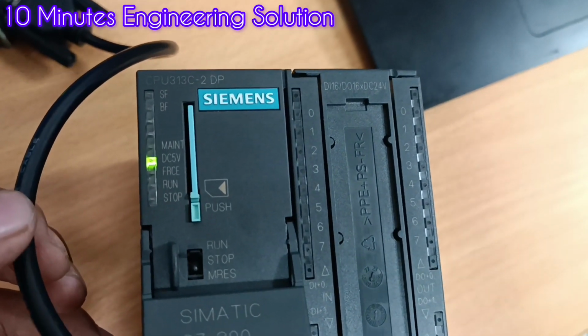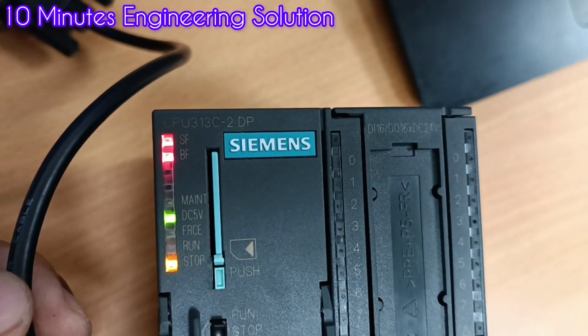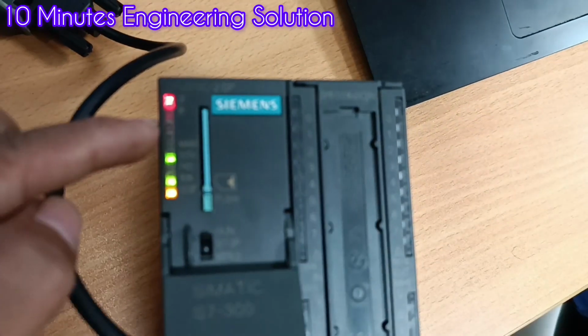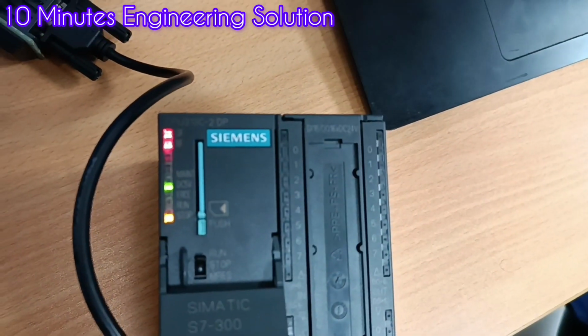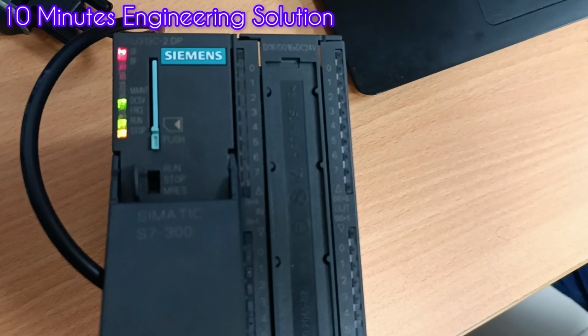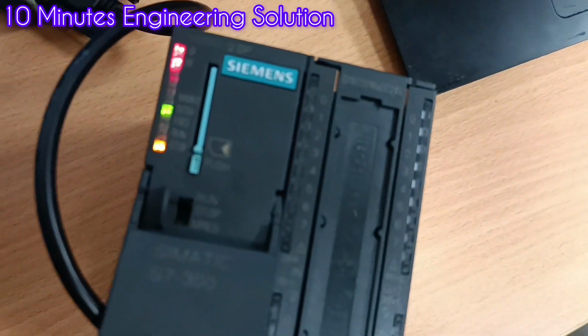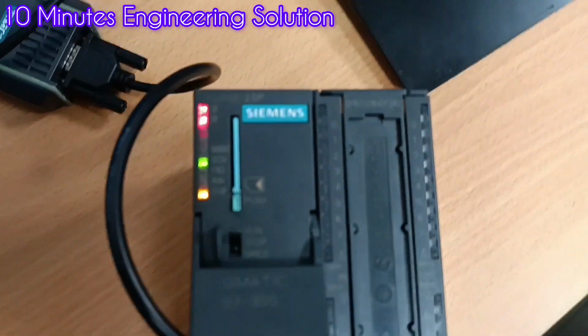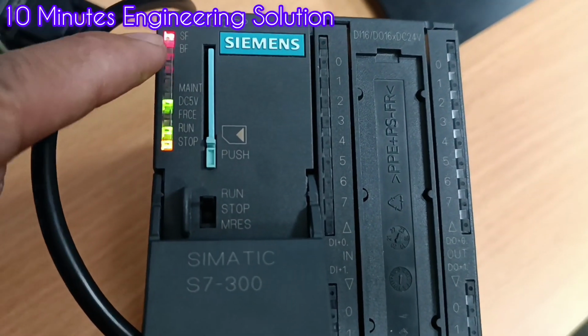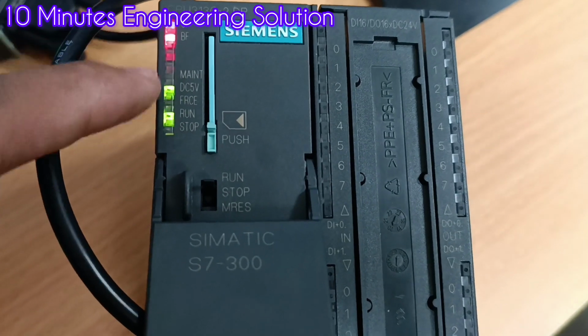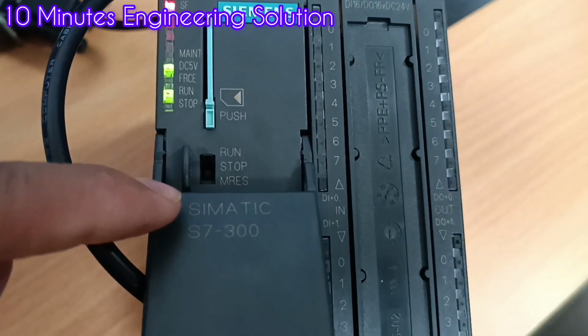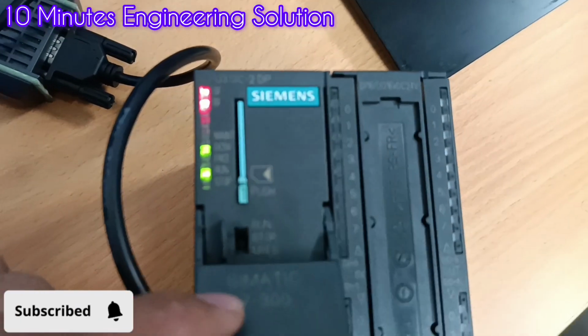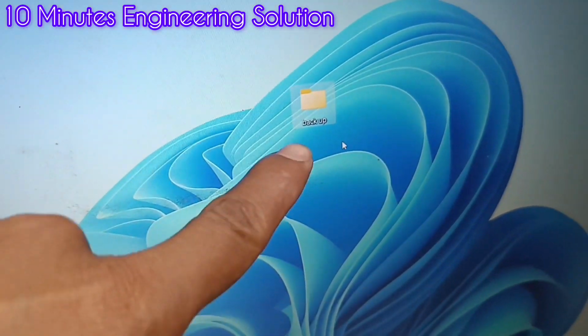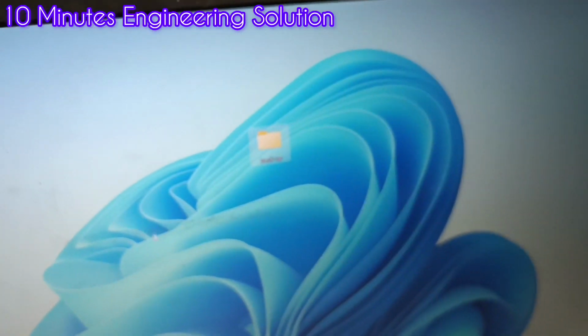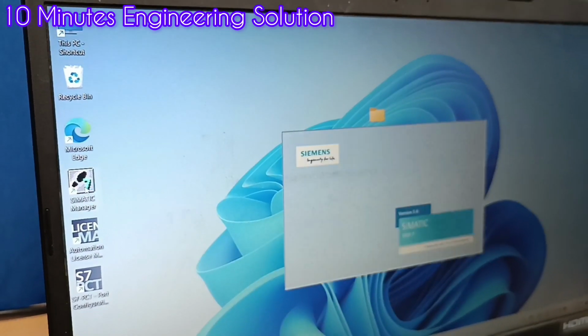See, the CPU is powered on. You can see here the system fault, bus fault, because the bus is not interfaced. So for that reason, they are showing the alarm. It doesn't matter because we just need to upload the program of this system. So you can see it showing the alarm, no problem. Now we can make the upload from the PLC to PC.